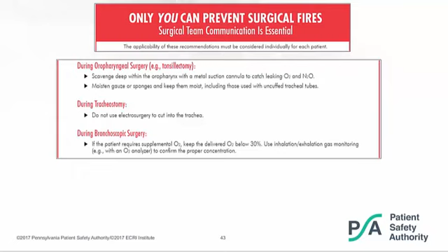As far as tracheostomies are concerned, it's important to understand that the way to prevent a fire during tracheostomy is to minimize the use of electrosurgery to actually enter the trachea. You do not want to do that, because that can be fatal. What can happen during tracheostomy is that since you have 100% oxygen inside the trachea, you can wind up accidentally igniting the tracheal tube or the cuff, and I'll show you a case review of that in a moment. You should only use electrosurgery to cut down to the trachea, but then scalpel or scissors to go into the trachea.